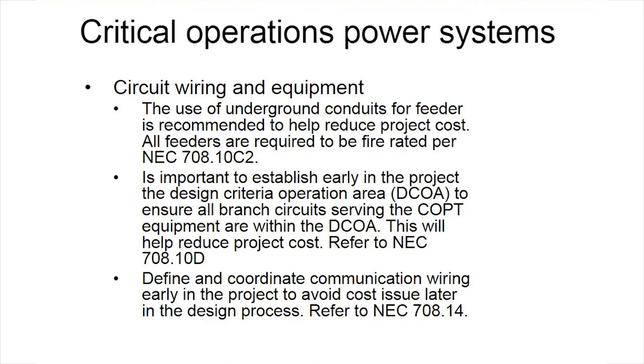It's also important to discuss communication wiring and how you're going to protect that wire. For COPs facilities, NEC 708.14 asks that the communication wire should be protected and should be fire rated. That is a significant amount of cost, and it needs to be discussed early in the process. And if that's the case, consider going on the ground with some of those wires. That way you will be able to protect it.